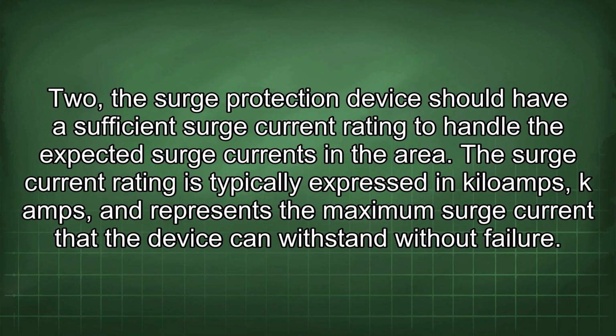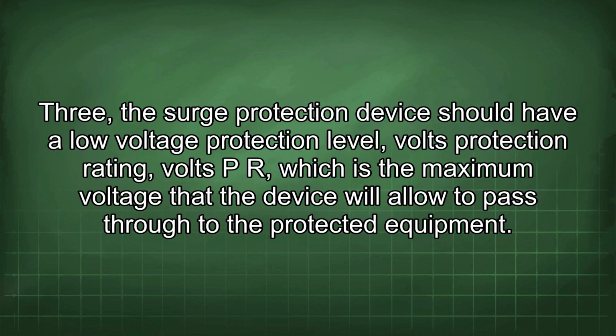2. The surge protection device should have a sufficient surge current rating to handle the expected surge currents in the area. The surge current rating is typically expressed in kiloamps, kA, and represents the maximum surge current that the device can withstand without failure. 3. The surge protection device should have a low voltage protection level, volts protection rating, volts PR, which is the maximum voltage that the device will allow to pass through to the protected equipment.